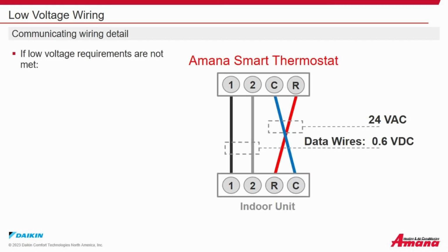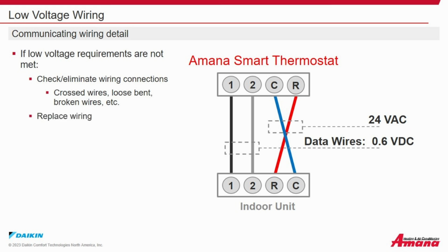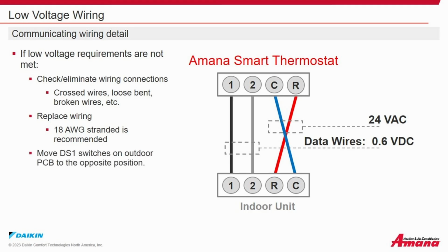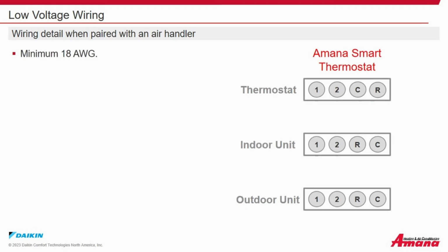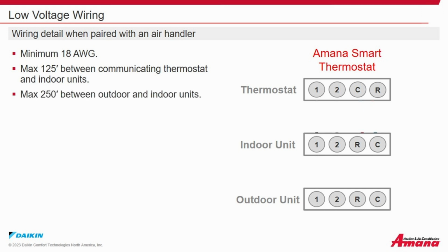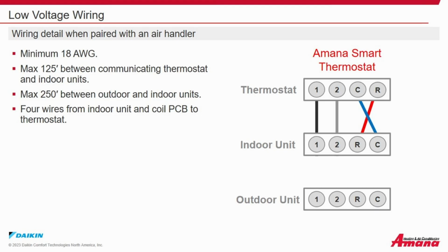Low voltage wiring. Communicating wiring detail. If the low voltage requirements are not met, check for and eliminate wiring connections, crossed wires, loose, bent or broken wires, etc. Replace the wiring. 18 gauge stranded is recommended. Move dip switch 1 on the outdoor printed circuit board to the opposite position. Low voltage wiring. Wiring detail when paired with an air handler. Minimum of 18 gauge wire. Maximum 125 feet between communicating thermostat and indoor units. Maximum of 250 feet between the outdoor unit and the indoor units. 4 wires from the indoor unit and coil printed circuit board to the thermostat. 2 wires to the outdoor unit.